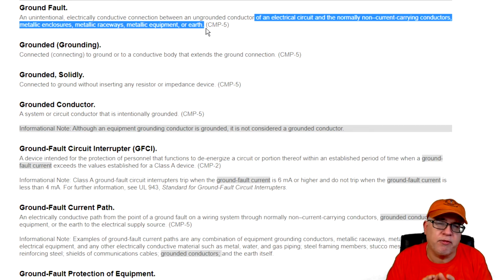Okay, so a ground fault is an unintentional connection between any of the ungrounded conductors and the metal enclosure, metal raceways, metallic equipment, all of which, under normal conditions, were intended to be non-current carrying. Under a fault condition, it's going to carry current, hopefully briefly, but under normal conditions, it's not designed to carry current.